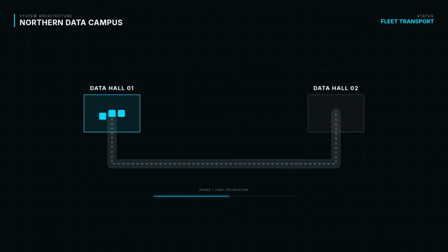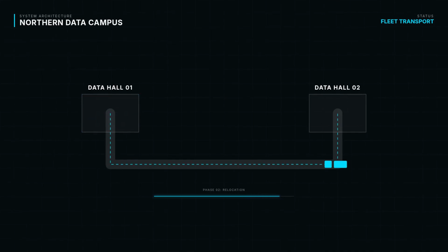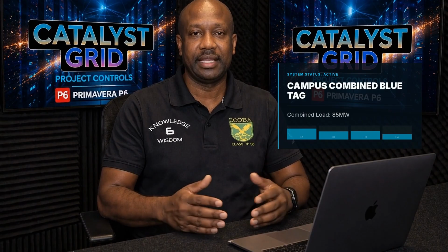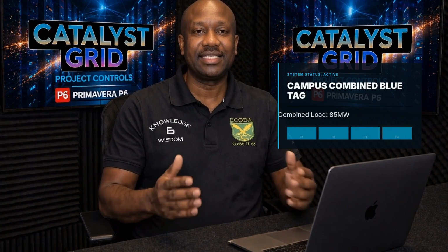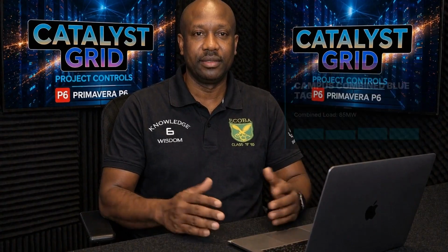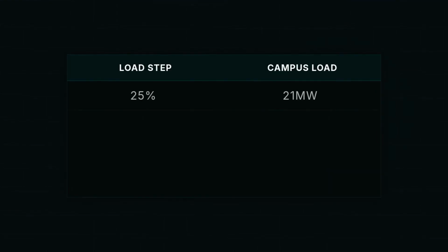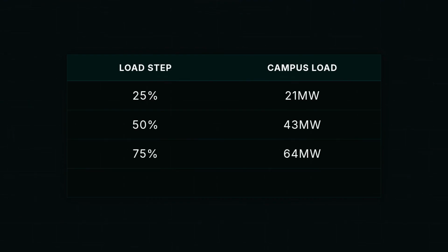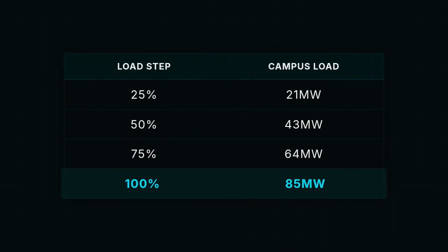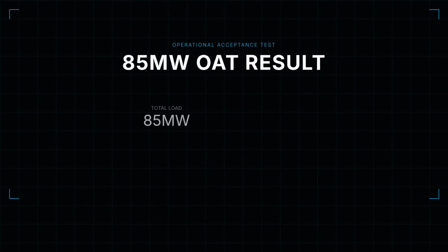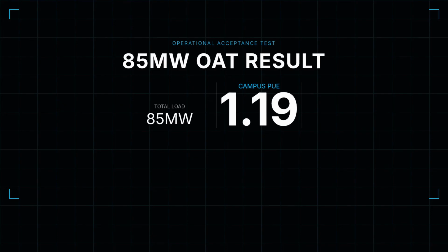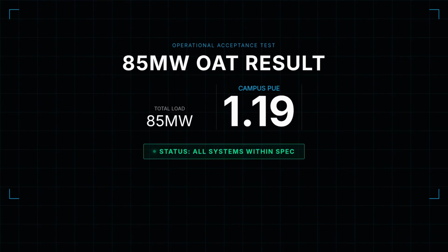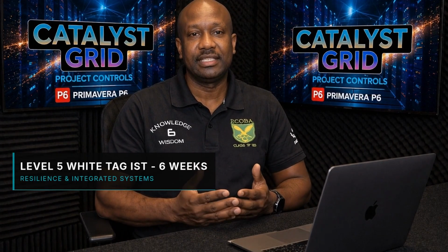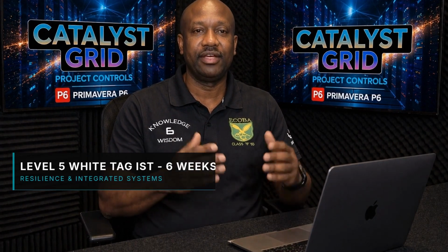The load bank fleet is then transported across the campus to follow the same schedule for Hall 2. The campus-wide combined blue tag loads all 4 halls simultaneously. This tests the shared infrastructure under full campus demand. We are testing the BSP loading, the on-site substation, and the waste heat recovery system under maximum heat rejection. At 100% load across all 4 halls, we reach 85 megawatts. This is the ultimate test of the shared high-voltage infrastructure. The blue tag OAT result was exceptional, a campus PUE of 1.19 with cold aisle temperatures across all halls within ASHRAE specifications. Level 5, white tag integrated systems test is the most complex commissioning event ever conducted by this team.